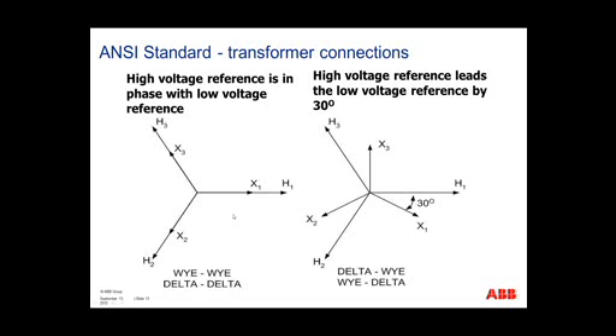So with the standard transformer connections, we can depict this vectorially. If you have a Wye-Wye or Delta-Delta connected transformer, you can see that the connections associated to H1, which is typically A phase, is in phase with the low side connections of X1, or A phase, low side. Similarly, high side H2 will be in phase with X2, and H3 in phase with X3. And this is for a Wye-Wye or a Delta-Delta connected transformer.